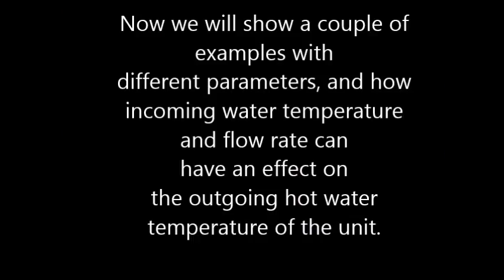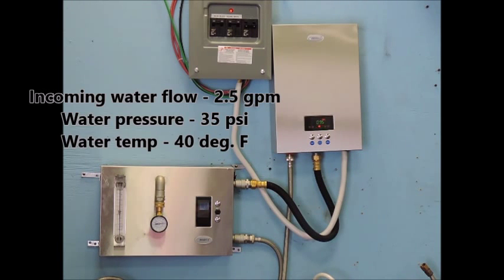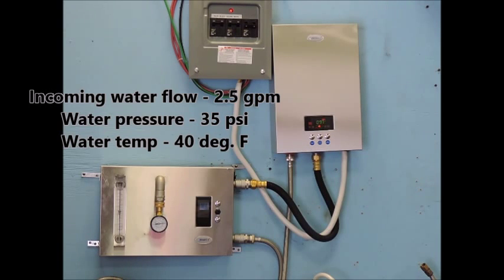Now we will show a couple of examples with different parameters and how incoming water temperature and flow rate can have an effect on the outgoing hot water temperature of the unit. In this shot you can see we have added an additional device to monitor our water flow, pressure, and incoming water temperature. When the display reads overflow, it is trying to tell you the incoming water is too cold to heat to the desired temperature at the speed it is moving through the heater, so we would need to reduce the flow of water.